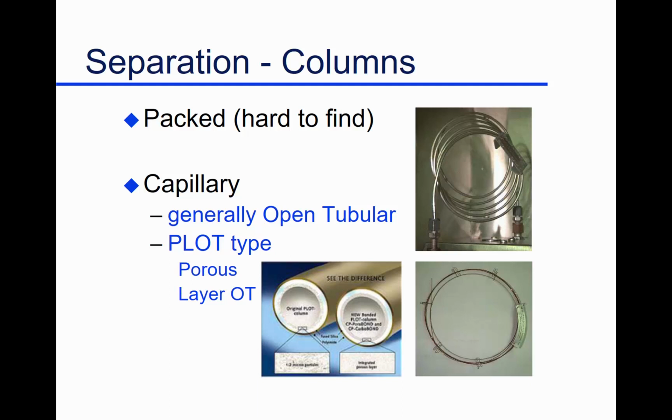And so we really didn't get good resolution, good separation with this. What we do instead is we actually go for an open tubular column. So here's my glass column. Here's my stationary phase. I've chemically bonded on the inside. That may be half a micron film thickness on here. So I put half a micron of my stationary phase on the inside of this very, very small column.